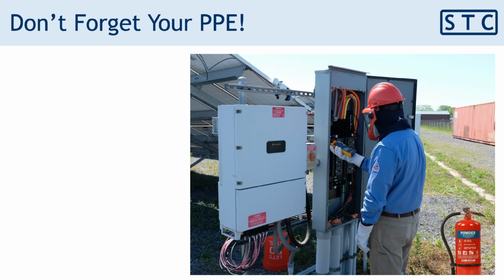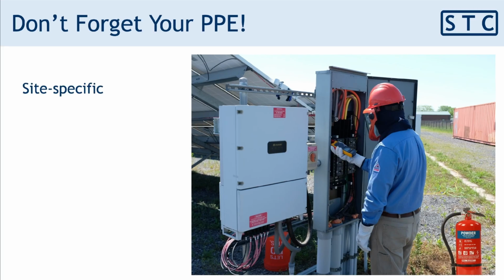Don't forget your PPE. PPE is site-specific. It depends on the hazards that are present at a particular site. For example, arc flash and shock hazards are going to be very particular to the level of energy that's present in a combiner box or an inverter cabinet or an AC panel board. And there should be labeling on all of this equipment. There are requirements for labeling so that you know the proper PPE to wear for working within the arc flash boundary and within the restricted approach boundary for shock hazards. You can see in the image on the screen, arc flash face shield, FR clothing, insulated gloves. All of that is appropriate based on the calculations done for this piece of equipment, which are site specific.